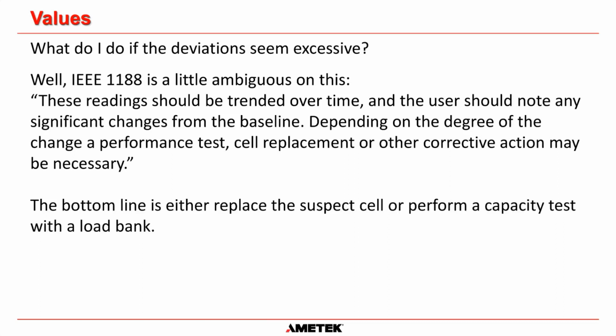So the bottom line is that if you see that a battery is definitely trending in the wrong direction and you can see it getting excessive, you must either replace that cell or perform a capacity test to prove the capacity of that cell. That is really the only two things that you can do. It may be much more cost effective to just replace a cell rather than do a capacity test and then replace the cell. But once again, that is up to the end user to decide which is the best way to go.